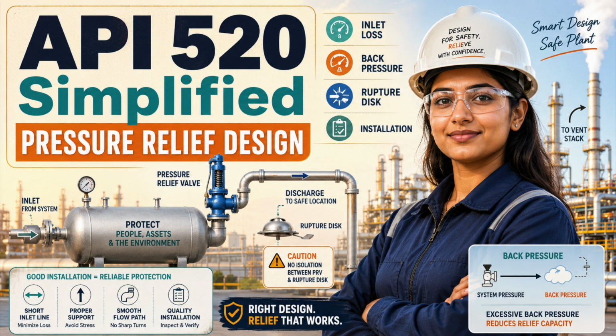Heat tracing must prevent freezing or solidification without overheating discs or seals. Insulation must not hide corrosion or leakage. Before installation, verify tag number, set or burst pressure, material, orientation, cleanliness, certification, flange condition, and transport damage. Protect pilot passages and sensing lines from debris. A safety device damaged before startup may remain invisible until the day it is required to save the plant. That is the central lesson of API 520.